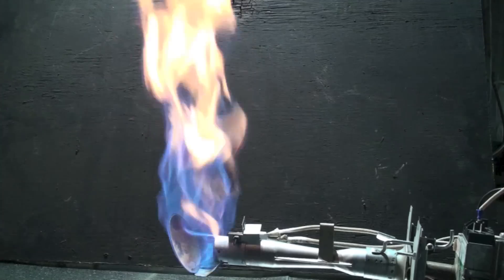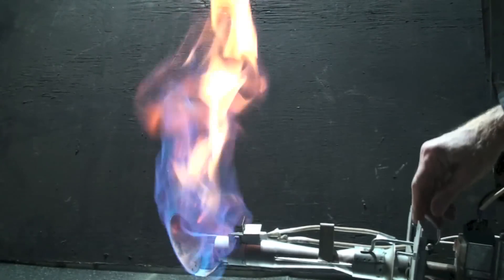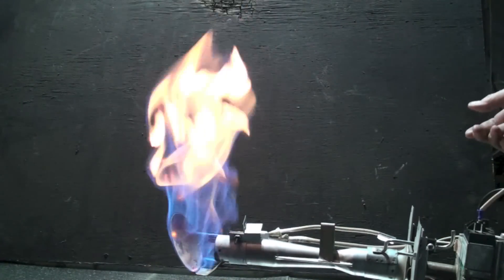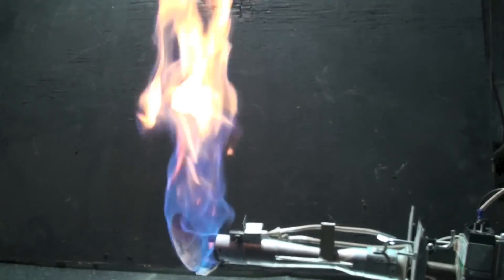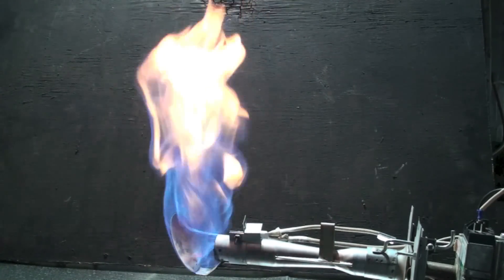Now you can see there's a lot of yellow in that flame. Now you can see I've opened this when I have the primary air pretty much closed. A lot of yellow in that flame.